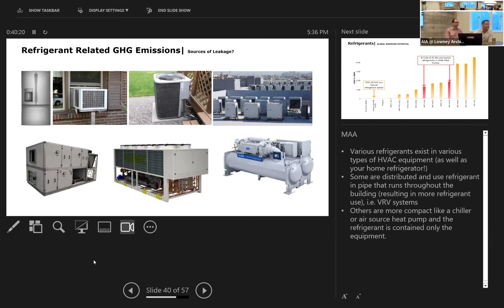So there are two things that matter here: the type of refrigerant and the amount. As we go to the next slide, there's substantially more refrigerant with VRF, and because you've got all of that extra piping, there's a bigger chance of it leaking as well. As we look at this graph, you can see on the right the typical refrigerants used today, these two, R410A and R134A. The important thing is to look on the left, the 100-year global warming potential of these refrigerants.